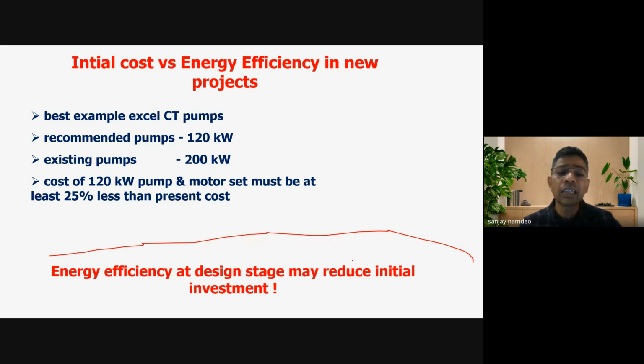So here is another example. In industry, there were very large cooling tower pumps, right? The existing pump was of 200 kilowatt with some parameters of head, flow and power. And when we did the audit of this plant, what we found is that this pump is over-designed, and the correct size would have been only a 120 kilowatt motor, and based on that, the rating of the pump, that is head and flow, would have been different. So what is the issue in this plant?